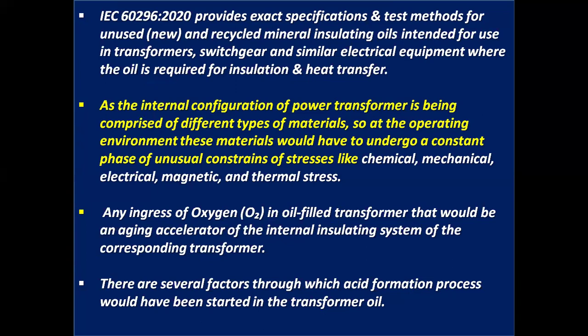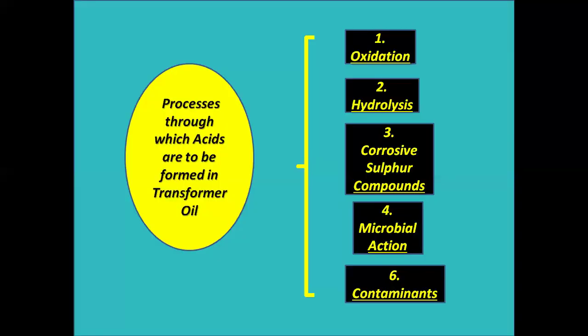There are several factors through which the acid formation process would be started in transformer oil. Say, the processes through which acids are formed in transformer oil: number one, oxidation; number two, hydrolysis; number three, corrosive sulfur compounds; number four, microbial action; number five, contaminants.